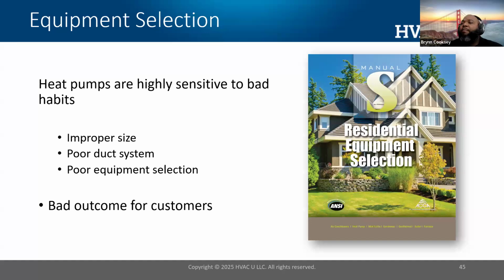The third manual we need to look at for proper design is Manual S. Did we select the right equipment for our customers? There's guidance in ACCA Manual S to help us identify the heat pumps, what size, the equipment selection to make sure that we select the right equipment for our application. Heat pumps are highly sensitive to improper size and poor duct design, and if we select the wrong equipment, it's going to be bad outcomes for customers.